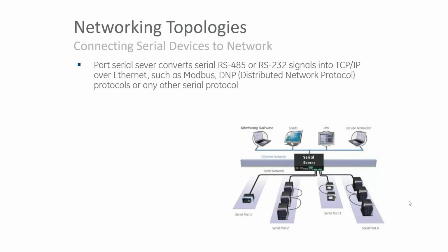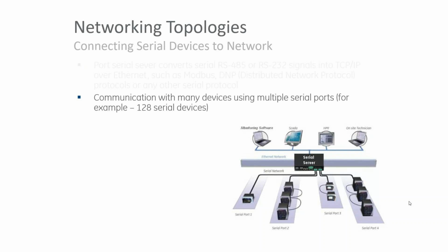You don't have to basically scrap your serial network just because you're upgrading something and you want it to go into Ethernet. And there are devices that we call serial servers, or serial translators, to be able to do that, so they can translate that serial protocol into the Ethernet version of that protocol. So we can have RS-485, 232, DNP, Modbus, and it can communicate to many devices, some of them up to 128, depending on the serial server or the serial transceiver device.